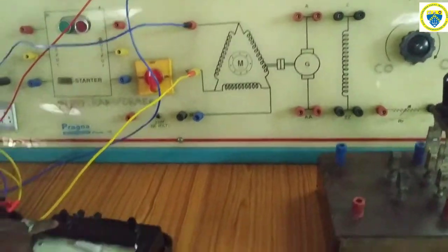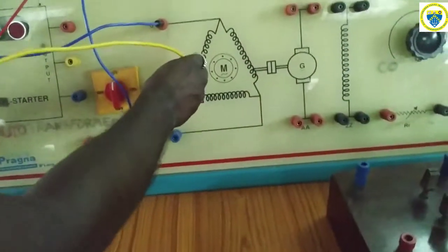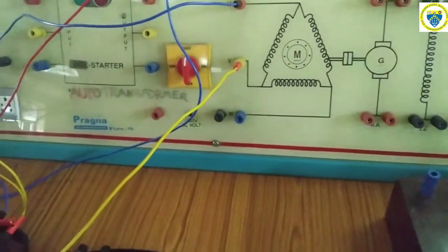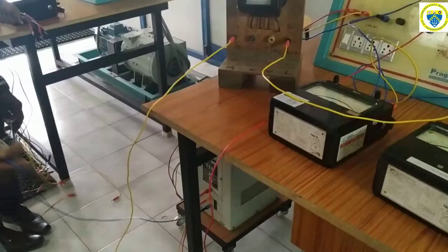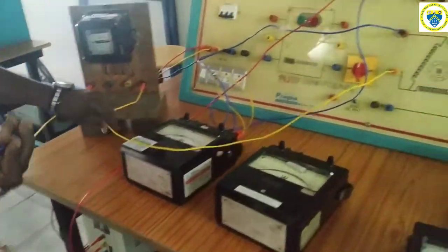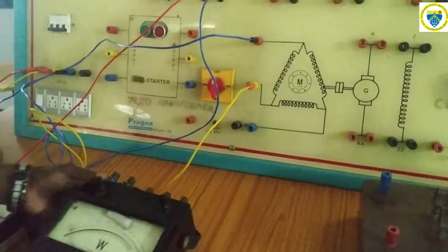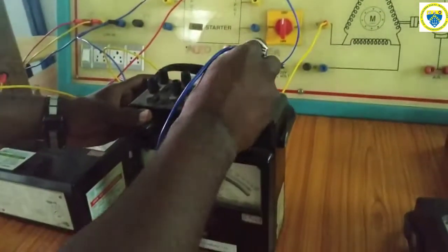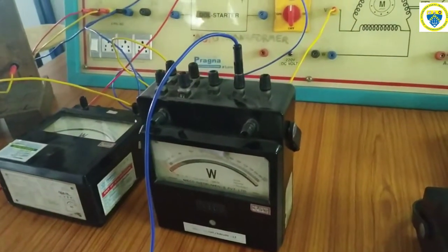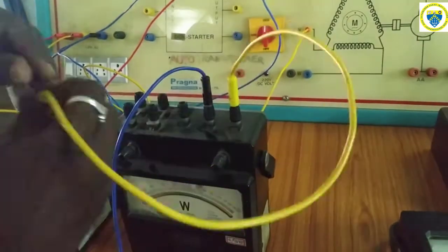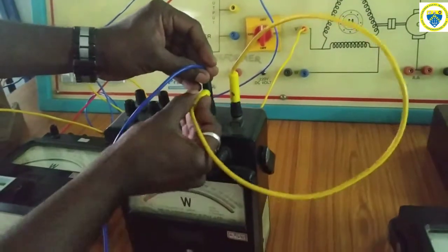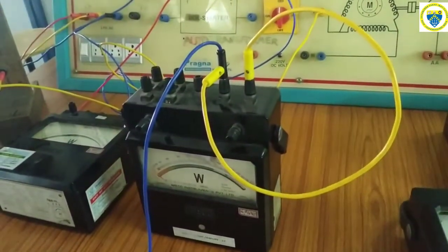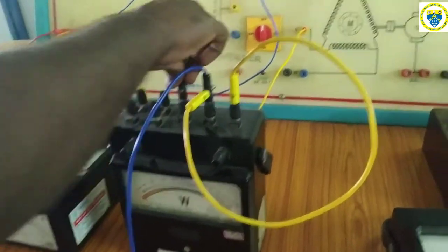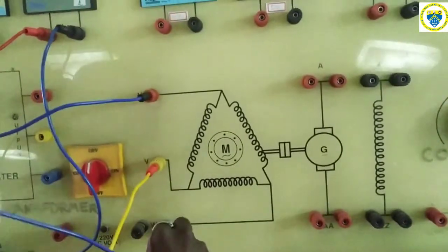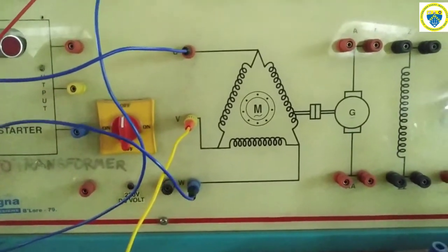Next, the B phase of the auto transformer should be given to the M terminal of wattmeter 2, and here also the MC terminals of the wattmeter should be shorted, and then the L terminal should go to the W terminal, meaning the third terminal of the induction motor.